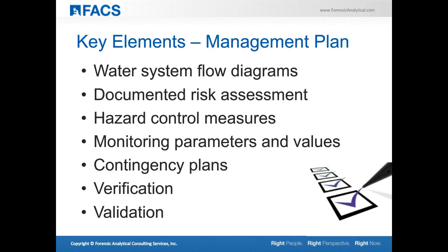Those key elements are very common among all the guidelines: having water system flow diagrams available, having a documented risk assessment specific to the building in question and the systems present, development of hazard control measures to control amplification for each area of risk, establishment of monitoring parameters and values to check the validity and efficacy of your program through testable parameters, and establishing a contingency plan in case those risk controls break down and amplification occurs.